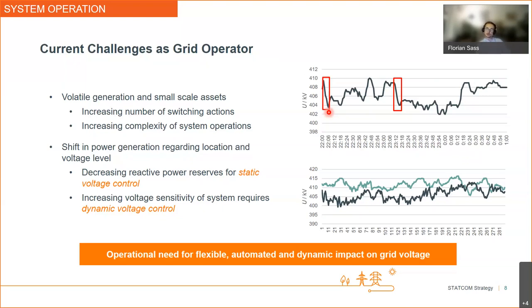And the figure below is the same substation. One measurement was done in wintertime, and one was done in summertime. And you can see that the voltage profile is highly different. With voltages of between 405 and 400 kV, this is a high transit scenario, so the voltage is at a modest level. But during low transit scenarios, the voltage is rising and is way higher, and we are not able to control the voltage anymore. It is still in a secure state, of course, the system. But you can see it's the same substation, and there's a voltage difference of roughly 10 to 15 kV, just depending on the scenario we're facing.